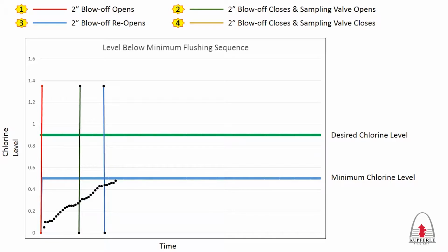Once the sample is obtained and analyzed, the station will do one of the following. If the sampled water's residual level is below the programmed minimum chlorine level, the unit will begin to flush all while continuing to sample. Once the sampled water's chlorine level reaches the programmed desired residual level, both valves shut off. Initial and final chlorine levels, time of day, and flush duration data is recorded onto the PLC.